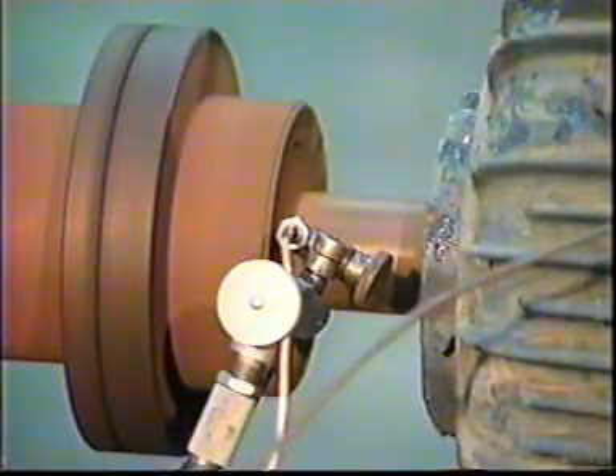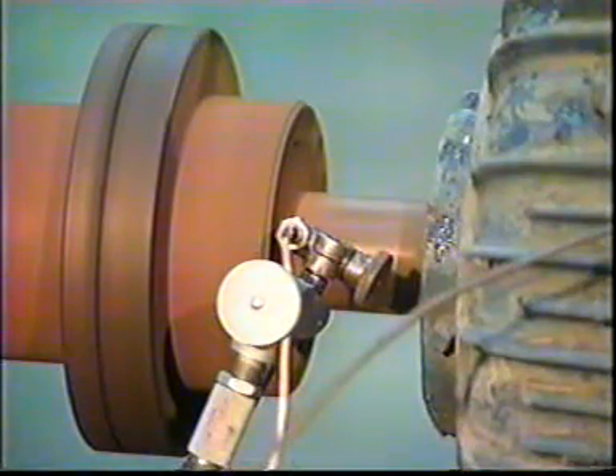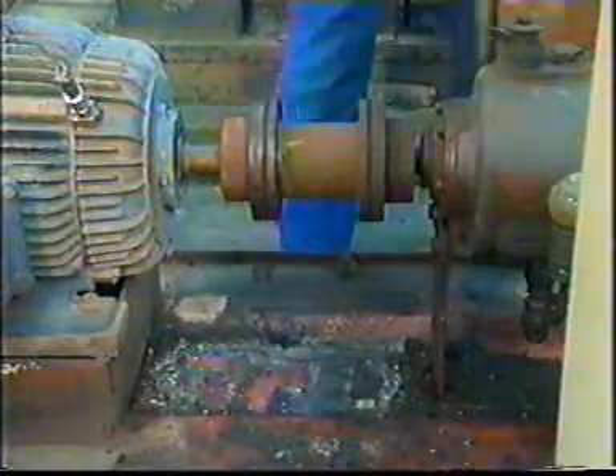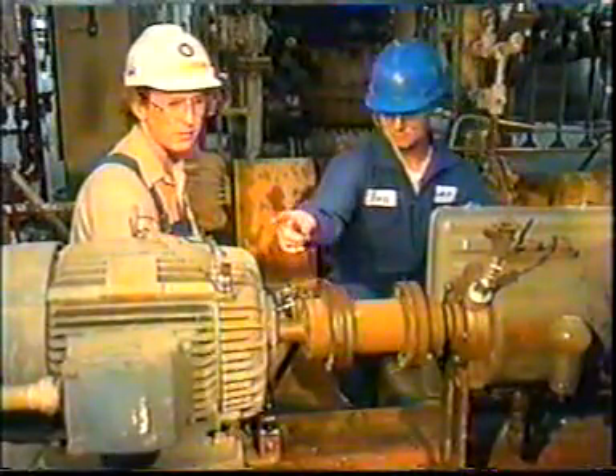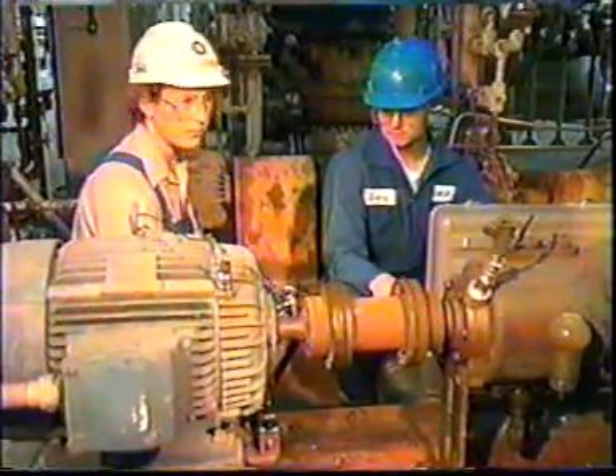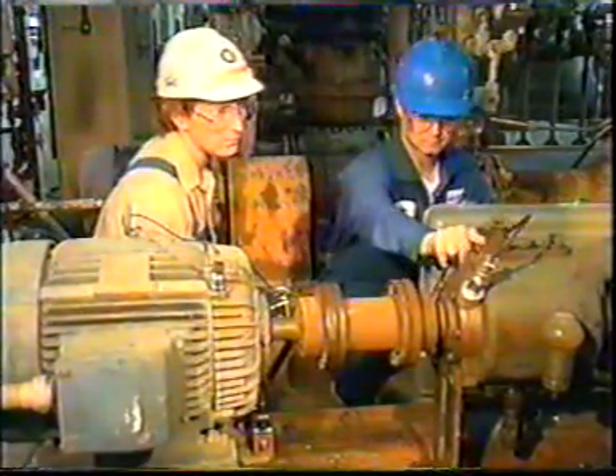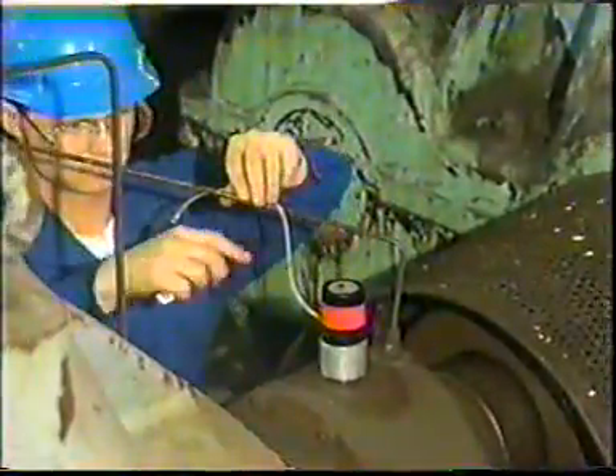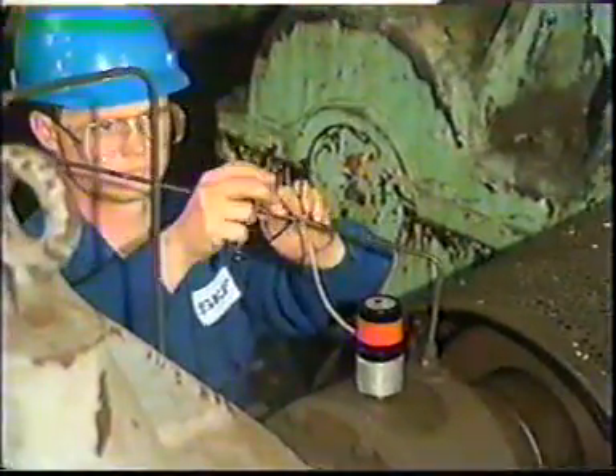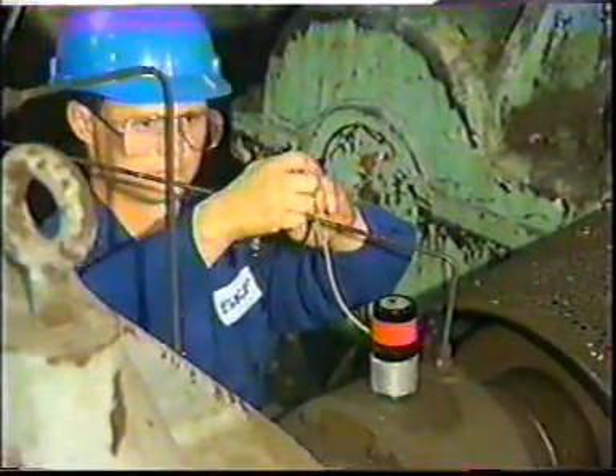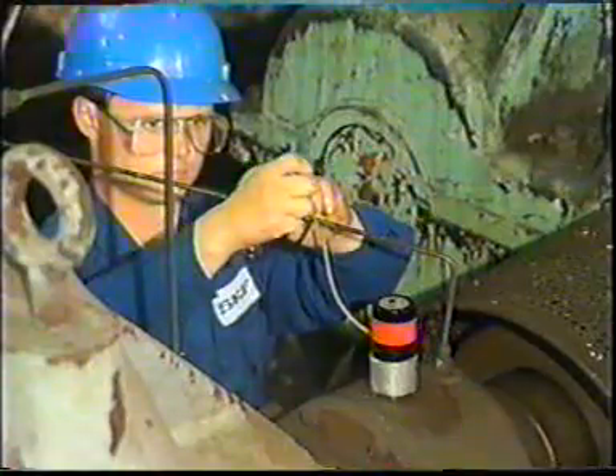Vibration measurement will often place you in very close proximity to exposed rotating machinery. In some cases, protective covers may be removed. Never work alone under such conditions. Be sure to have an operator who is familiar with the particular machine standing by, ready to shut the machine down. Follow your facility's safety precautions. Be sure to secure any loose clothing to keep from being pulled into the machine.